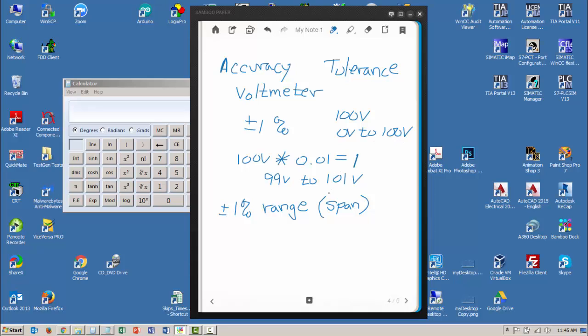But what this tells me is that this 1% is going to apply to any voltage I read on that scale, on that 100-volt range. So if I'm reading 100 volts, this is still a valid calculation.